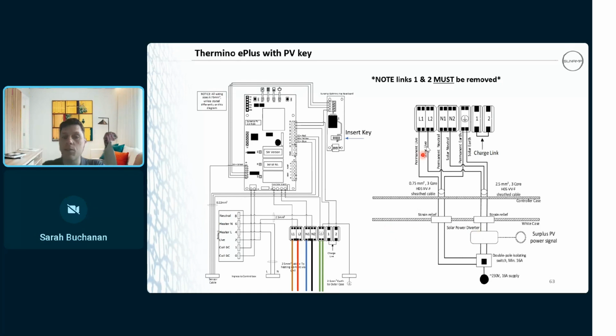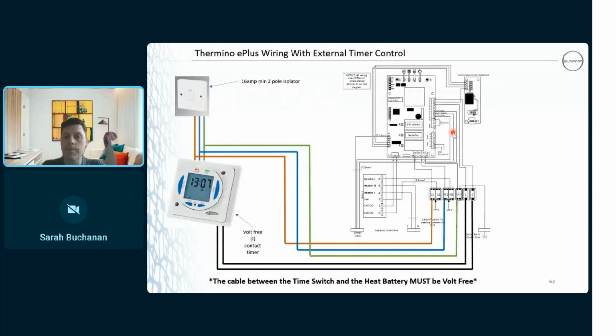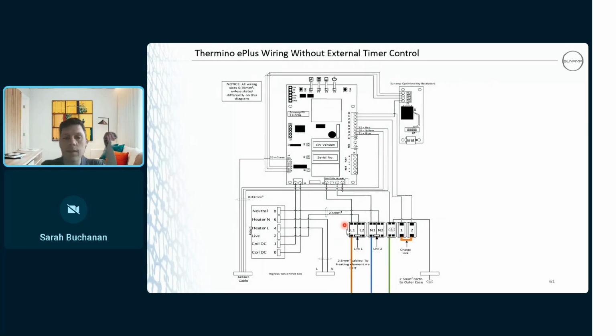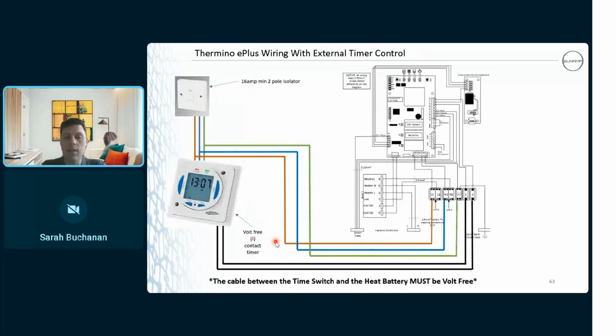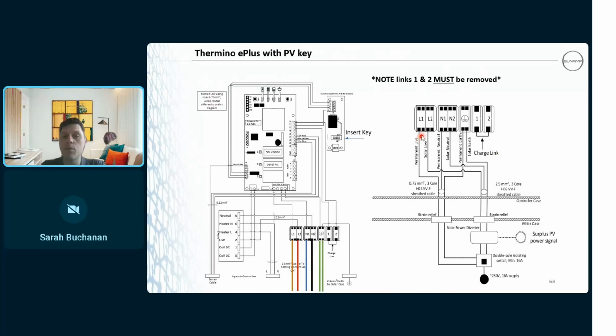All right, and then you remove the links. See, the links are missing there. So if we go back, you've got link 1, link 2. All we're doing is bridging that permanent live over to the start of this contactor, this relay. Whereas we remove the links, so we separate the lives and we separate the neutrals.